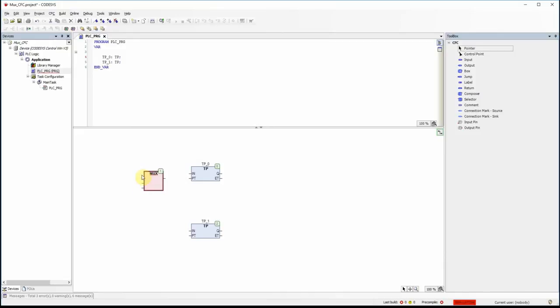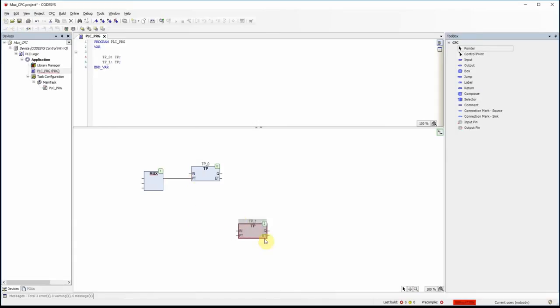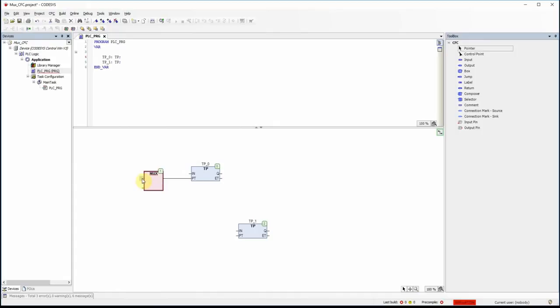By default the MUX has three inputs and one output. We can connect the output of the multiplexer to the PT input of the pulse timer. The MUX receives several inputs: the first input is an integer value — it could be 0, 1, 2, and so on — and based on that value one of the other inputs will be selected and appear at the output.